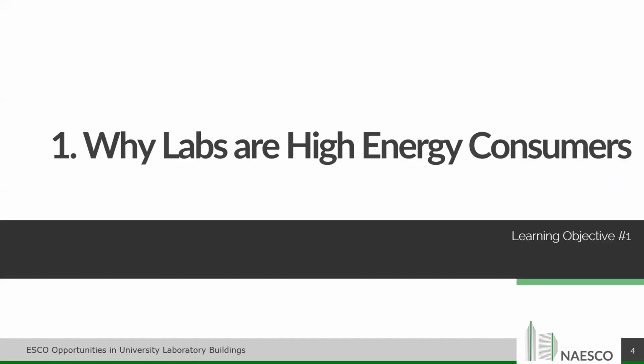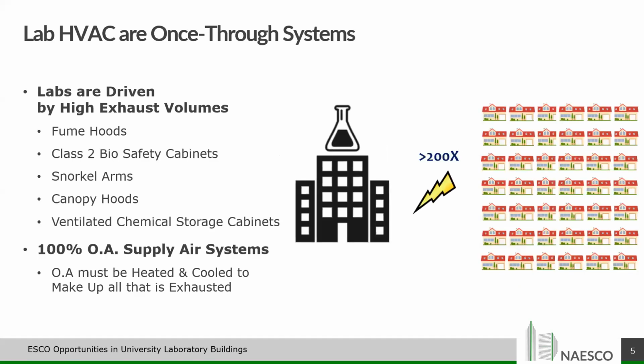So let's dive in. Why are labs such high energy consumers? Labs are very exhaust intensive. There's a great deal of equipment in labs that is designed to exhaust fumes from chemicals. The purpose is to keep the lab users safe. We've got fume hoods, biosafety cabinets, and just general exhaust in the lab space. This is not return air. This is exhaust air that's coming from the lab, going through the exhaust system, and being exhausted up through the roof of the building and out of the building.